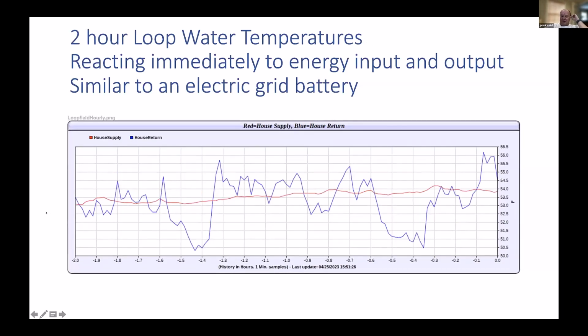Looking at this a little bit more granular, this is now 2 hours, and you can see how it jumps up and down. In this case, we are rejecting energy into the loop field because the entering water temperature is warmer than the temperature coming back from the loop field. And the loop field temperature coming back, it's pretty much equal. That means there's a huge thermal mass back there. And no matter if I take energy out or in, the battery is so large, it hardly is reacting to those instantaneous in and outputs.